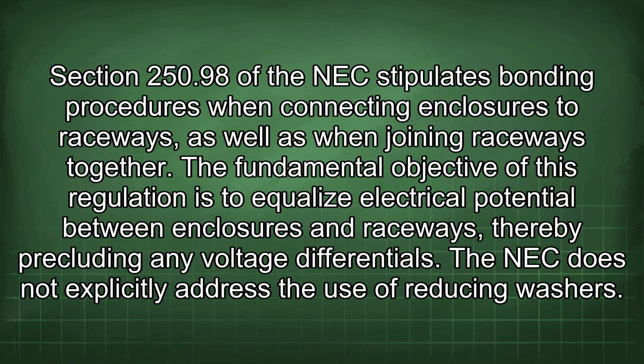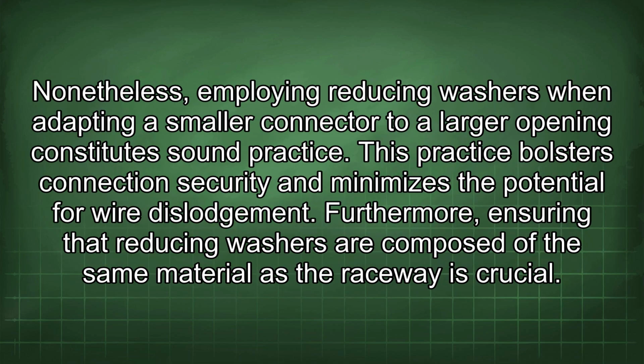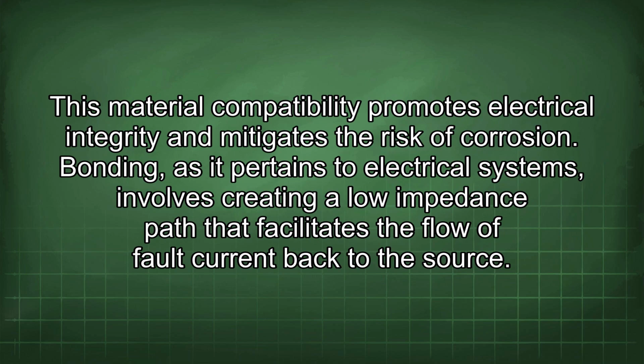The fundamental objective of this regulation is to equalize electrical potential between enclosures and raceways, thereby precluding any voltage differentials. The NEC does not explicitly address the use of reducing washers. Nonetheless, employing reducing washers when adapting a smaller connector to a larger opening constitutes sound practice. This practice bolsters connection security and minimizes the potential for wire dislodgement. Furthermore, ensuring that reducing washers are composed of the same material as the raceway is crucial. This material compatibility promotes electrical integrity and mitigates the risk of corrosion.